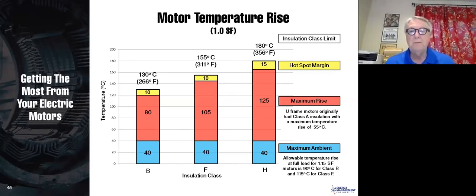So these days, typically most motors contain Class F insulation, and Class F insulation is rated for 155 degrees centigrade. So that is 40 degree ambient plus 105 degree rise plus a 10 degree hot spot. And as we mentioned last time, the hot spot basically says that there's somewhere in that motor that's going to be 10 degrees hotter than the average temperature inside the windings. So you just add that for a little bit of conservative calculation there. So that's 155.